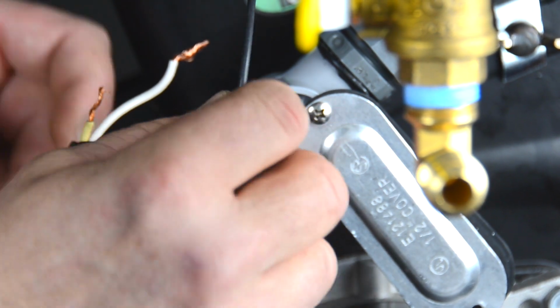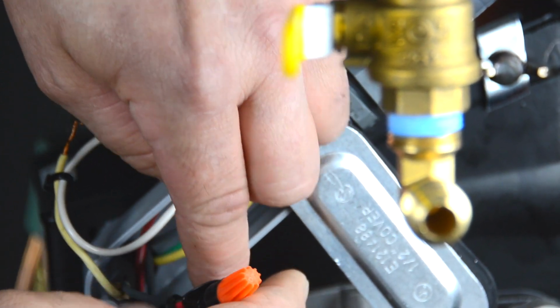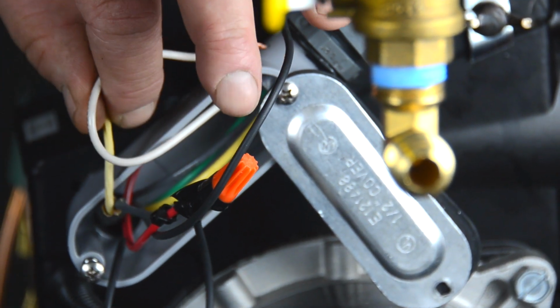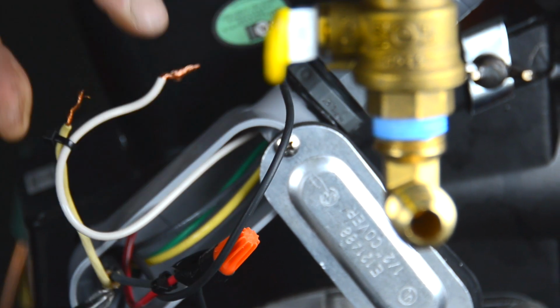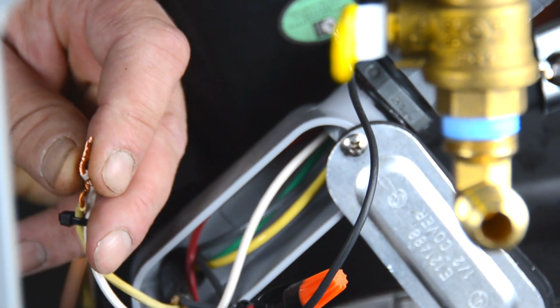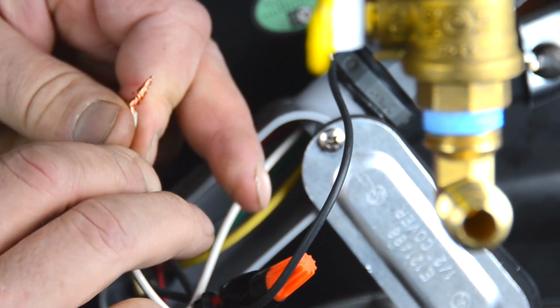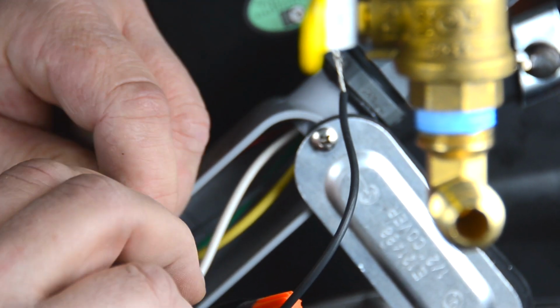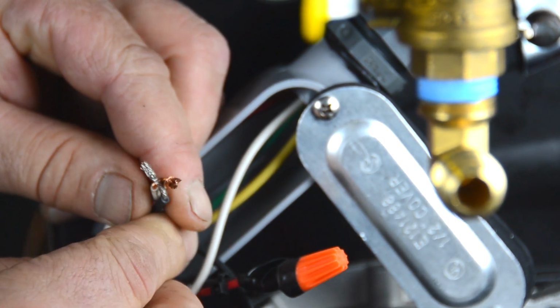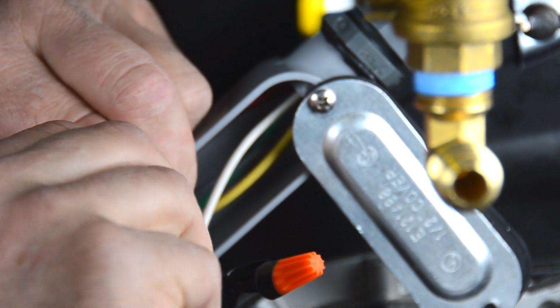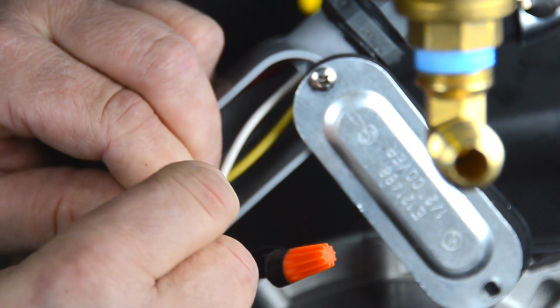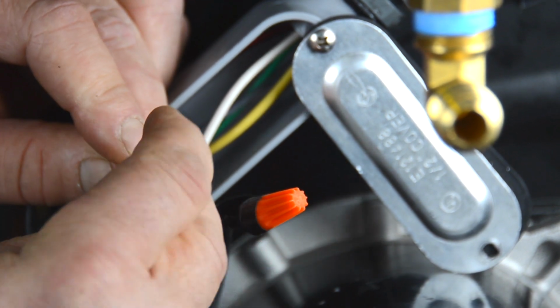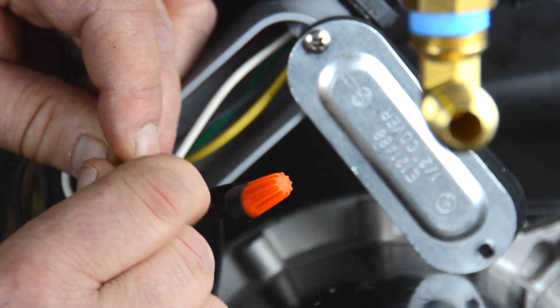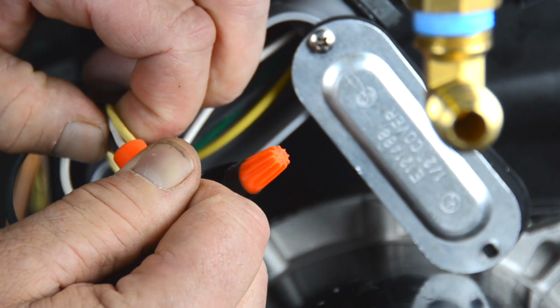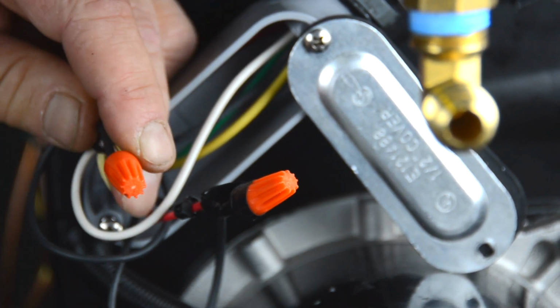Now, you have two white wires left. The one coming out of your burner power and the one coming down the conduit here. You're going to make sure that they're twisted up. Then take your other black wire from your transformer, and that goes right here. You're going to wire nut that, tape it also. Always check to make sure that your wires grab inside your nut, and tape it.